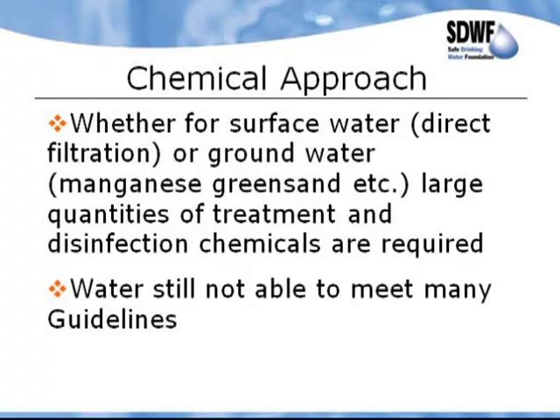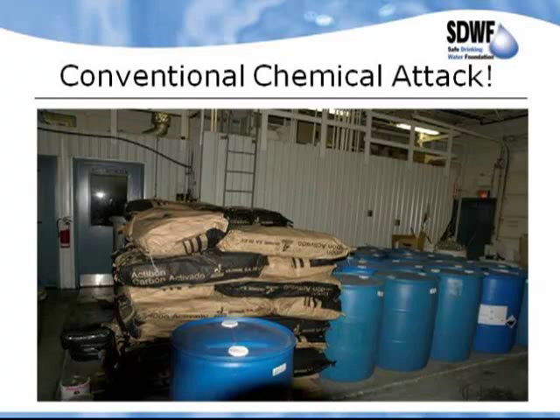The traditional way has been to use a chemical approach — whether for surface water using direct filtration, or groundwater using manganese greensand, we use large quantities of treatment and disinfection chemicals, and the water is still not able to meet many of the guidelines. Outside this lake they are using a tremendous amount of chemicals every month — producing about 250 gallons a minute of water and using $15,000 worth of chemicals a month. Despite having a Zenon ultrafiltration system, this community has been under a boil water advisory since 2004.